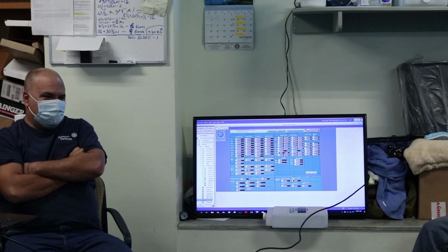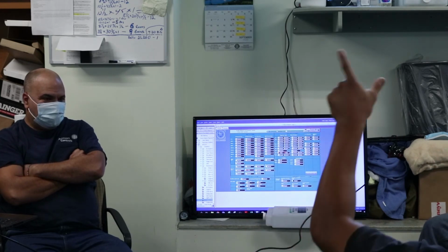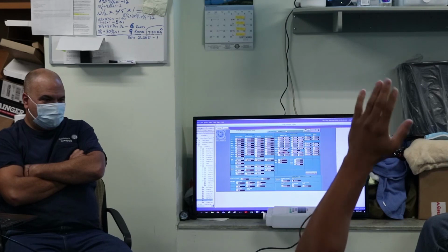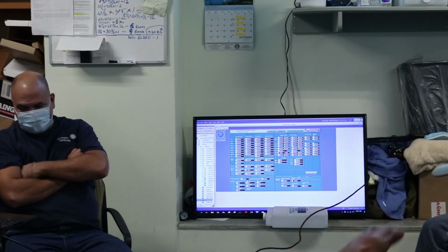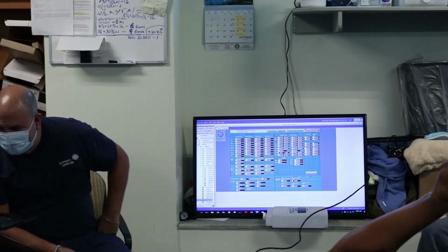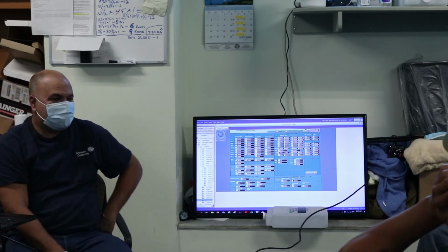It's amazing. Medications are supposed to be within a certain temperature, right? Exactly, but they put it in a closet. They look and say, oh, there's an exhaust in there. No, that's just open to the plenum. There's not an exhaust, and there is no supply.